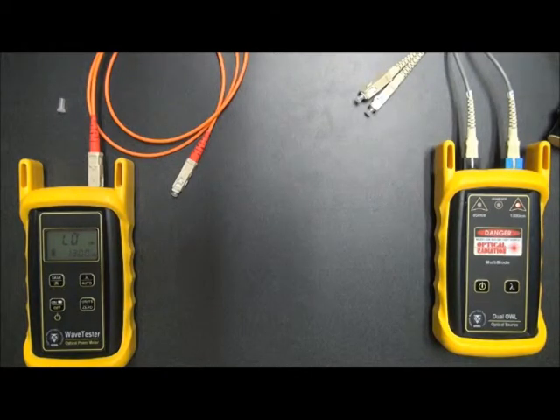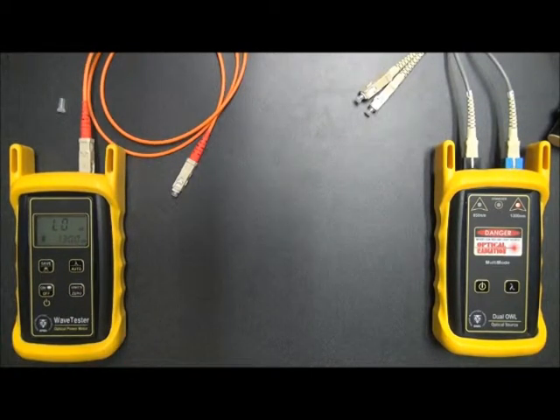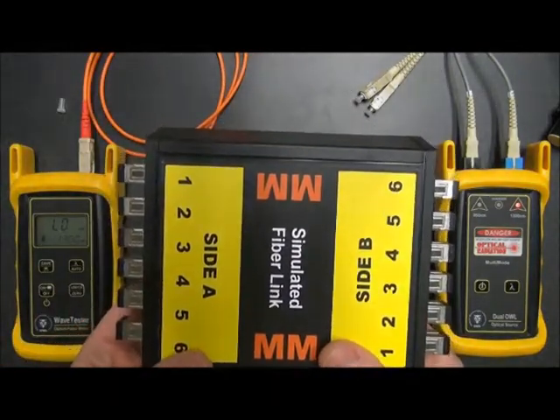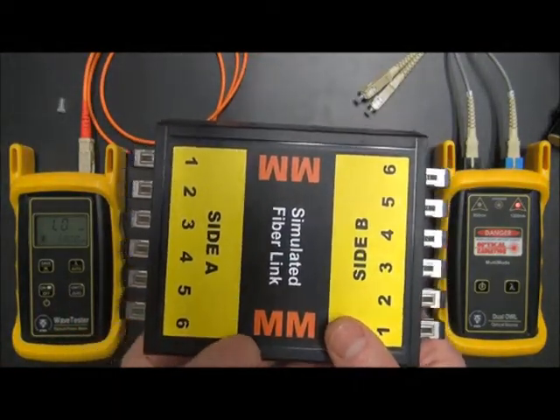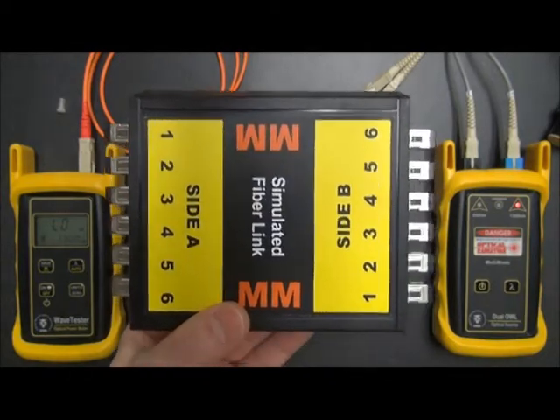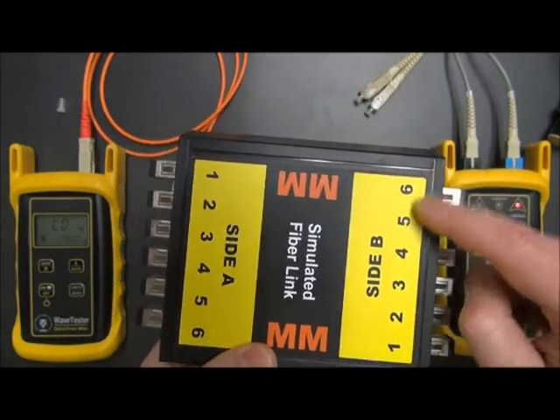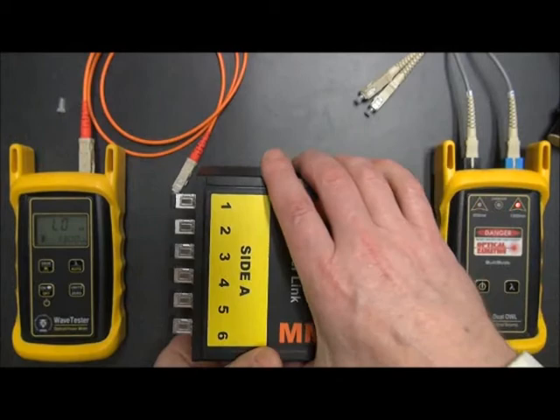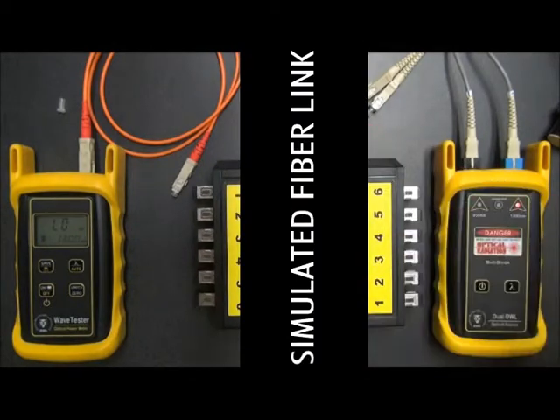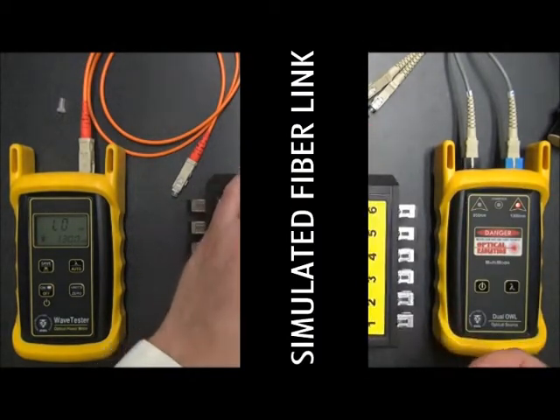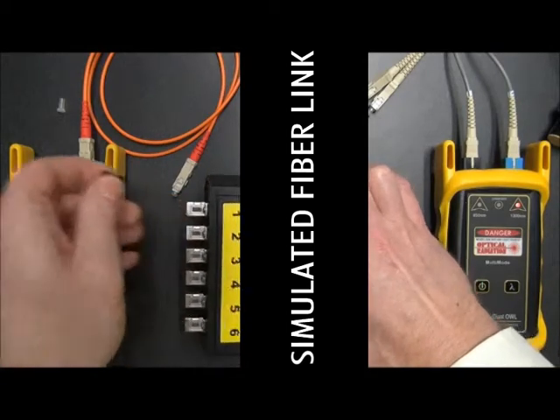Now, the next thing we need to do is connect into our link. And for this purpose, I have this little box here that kind of simulates a fiber link with a patch panel on either side. Now, in this case, we have a 6-port patch panel. There's 6 ports here, 6 ports there. We would need to first connect into port number 1 to take our measurement.